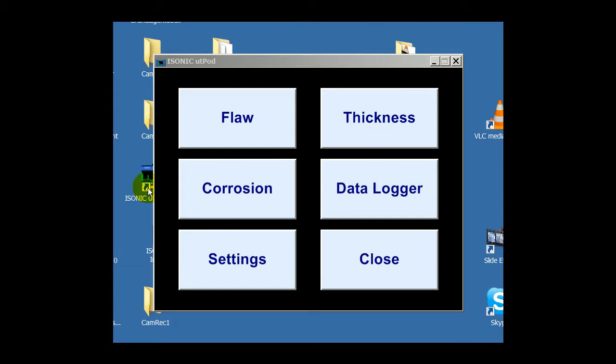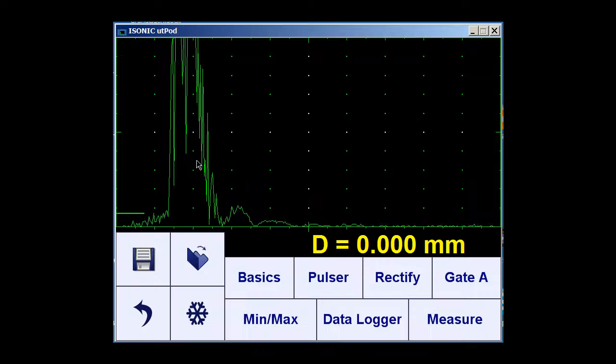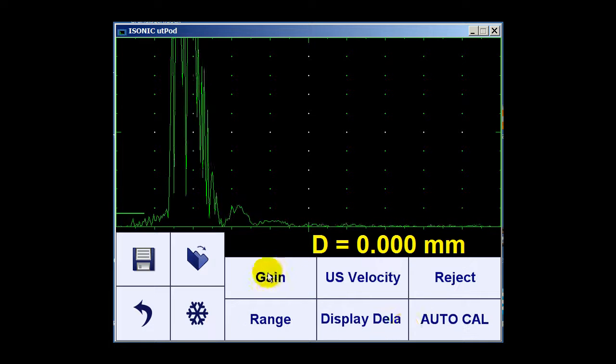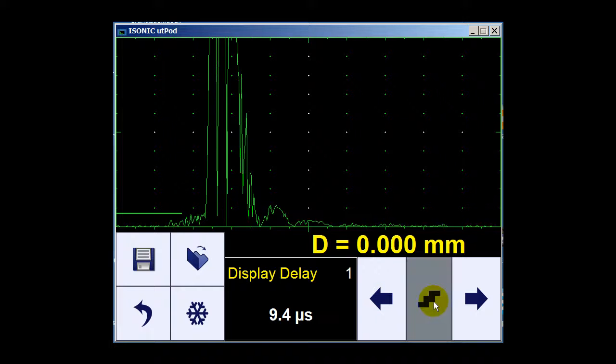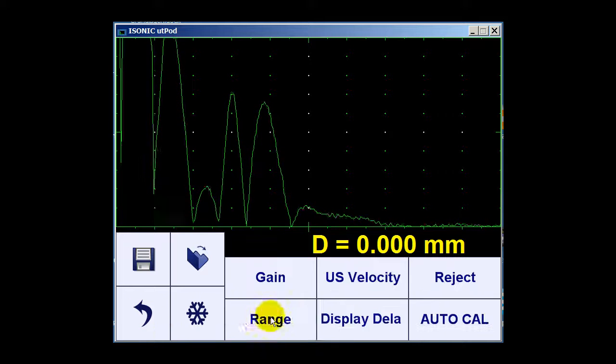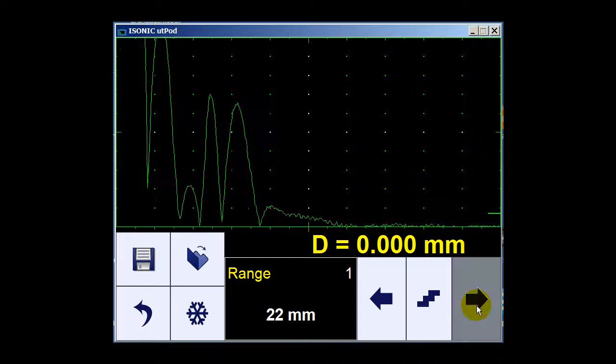First of all, from the main menu we select thickness, then we go to calibration. We have to set the display delay to zero first to make sure that we do the right adjustment right from the beginning.